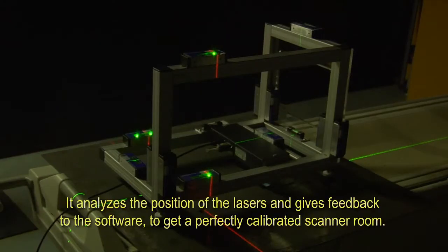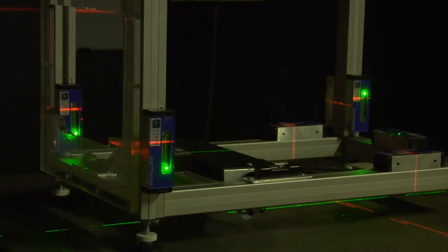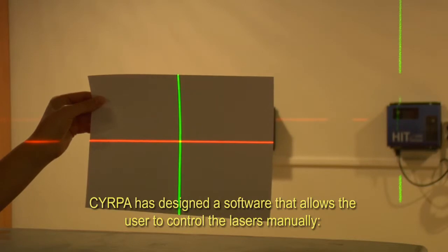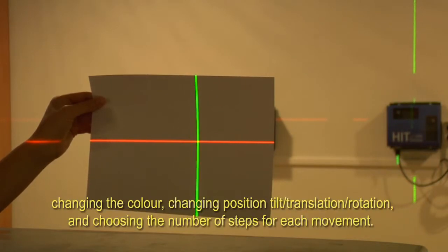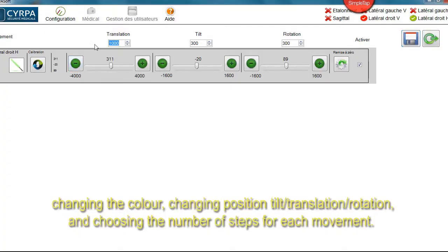The Smart Phantom CT analyzes the position of the lasers and gives feedback to the software to get a perfectly calibrated scanner room. CYRPA has designed a software that allows the user to control the lasers manually — changing the color, changing the position, tilt, translation, rotation — and choosing the number of steps for each movement.